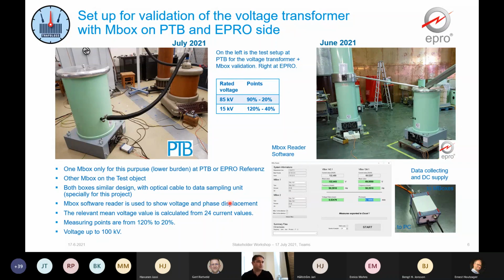And here we can see how the setup looks like in PTB and EPRO side. On both pictures, we can see the setup for the validation of the voltage transformer with Mbox. So both reference and the test object have digital readout. In the reader software, we can see two things. First, what are the current values of both boxes, and second, the phase displacement between them. The relevant mean value is then calculated from 24 current values.